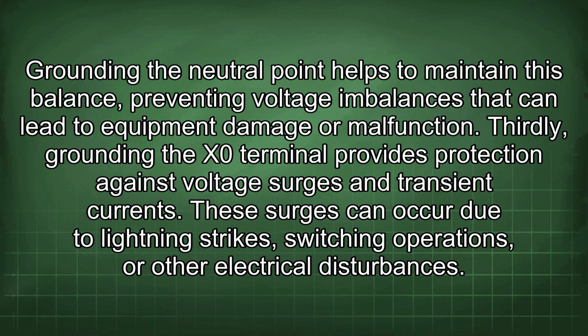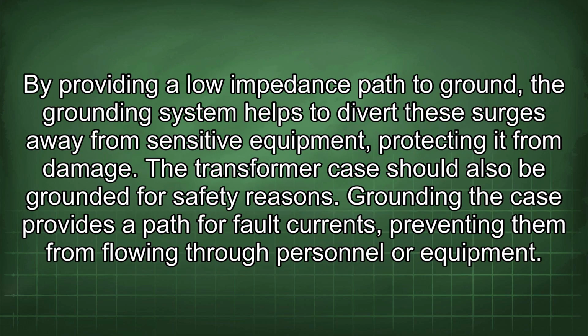Thirdly, grounding the X0 terminal provides protection against voltage surges and transient currents. These surges can occur due to lightning strikes, switching operations, or other electrical disturbances. By providing a low impedance path to ground, the grounding system helps to divert these surges away from sensitive equipment, protecting it from damage. The transformer case should also be grounded for safety reasons.